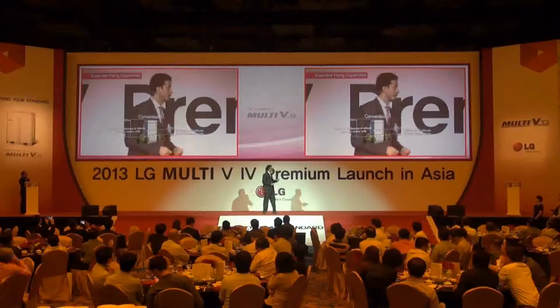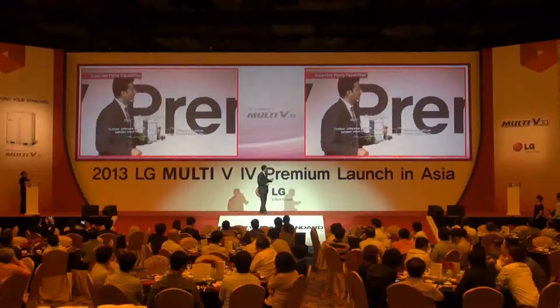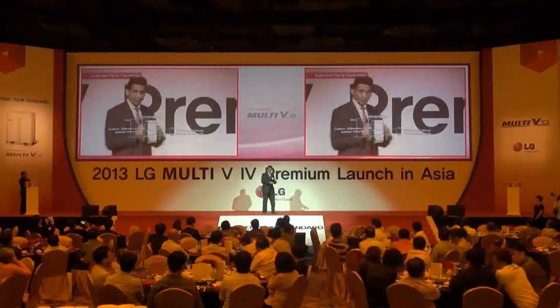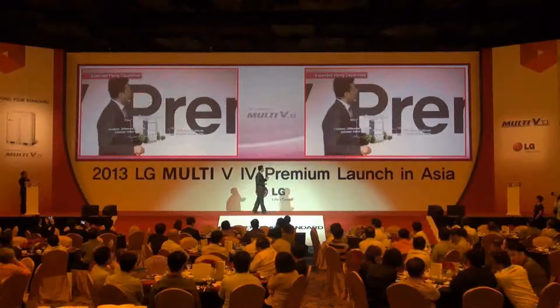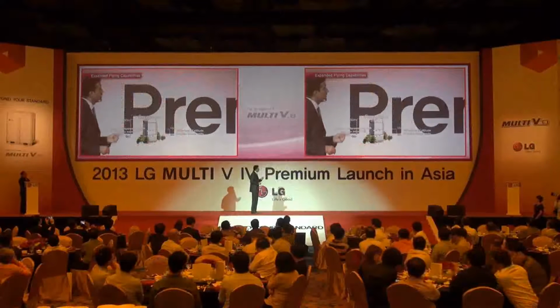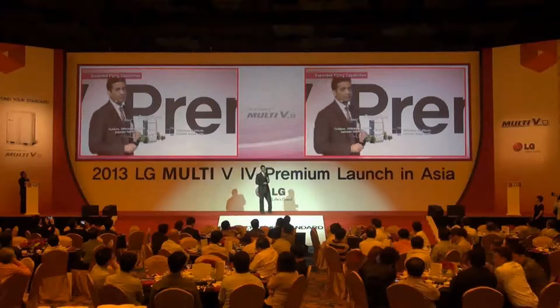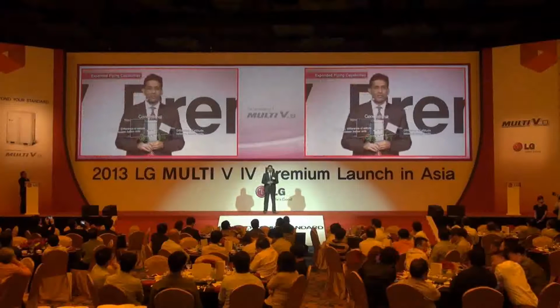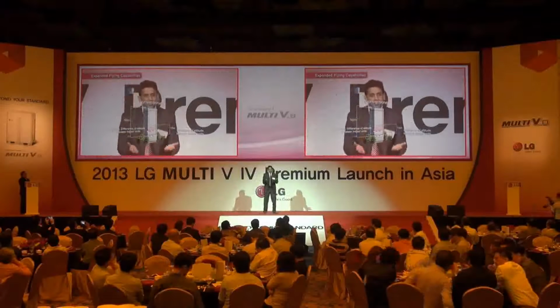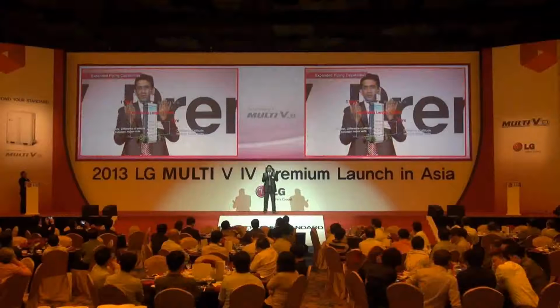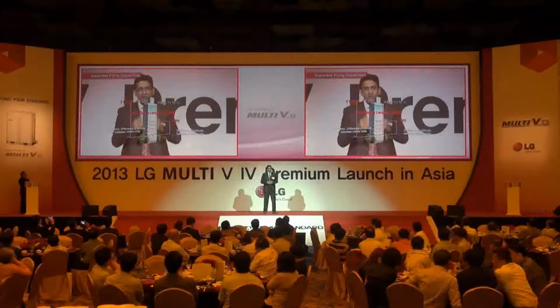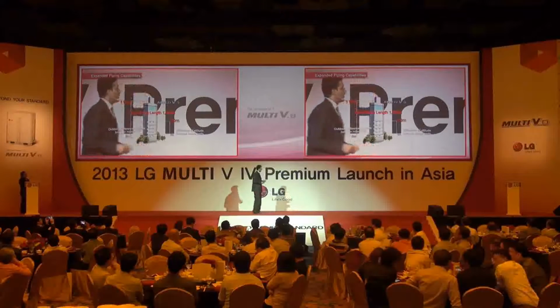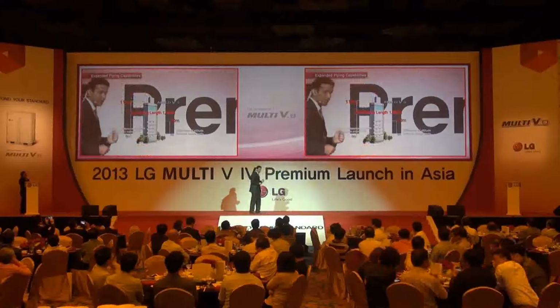Your indoor to indoor piping was just 15 meters, and indoor to outdoor single elevation was just 50 meters with conventional technologies. But now with our Multi-V, we have greatly improved the piping, making indoor to outdoor piping as long as 110 meters.